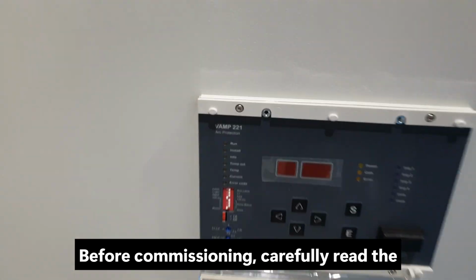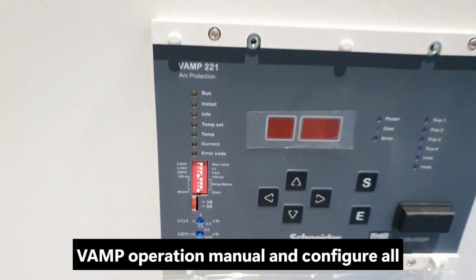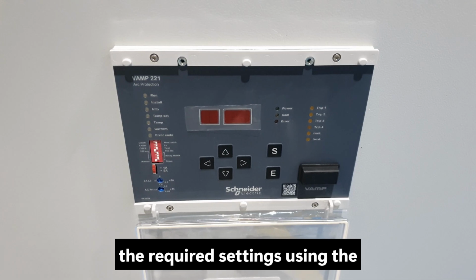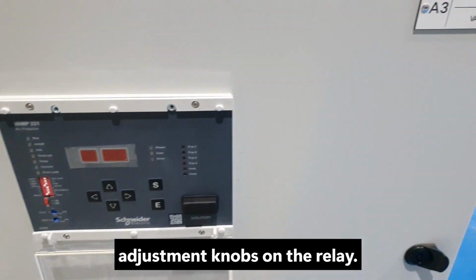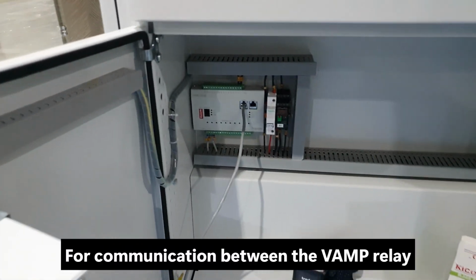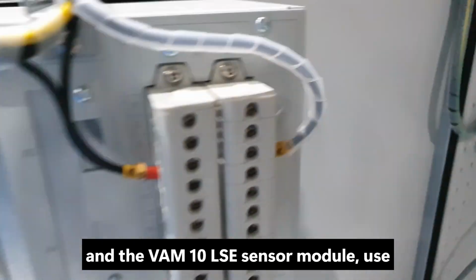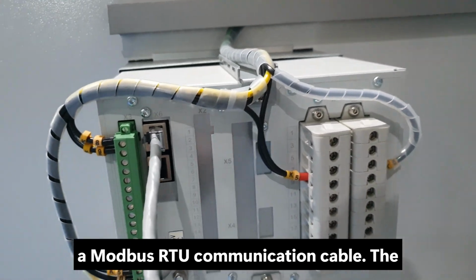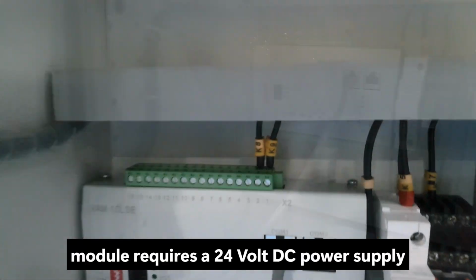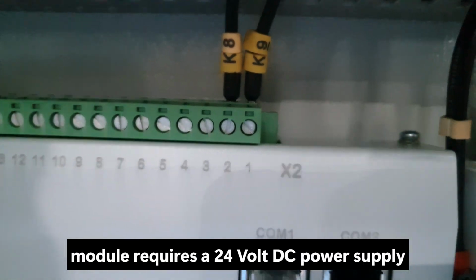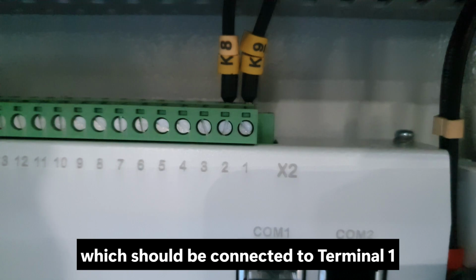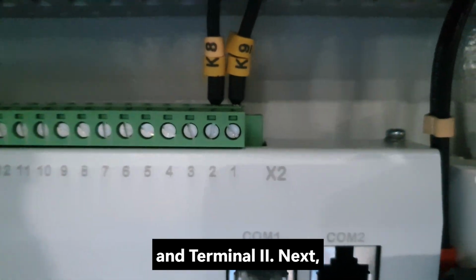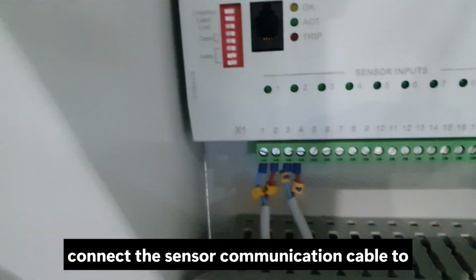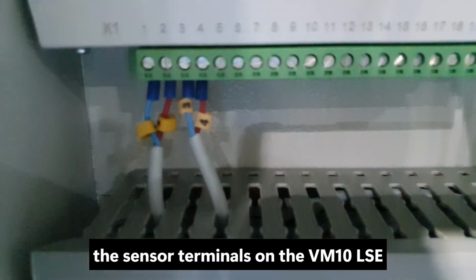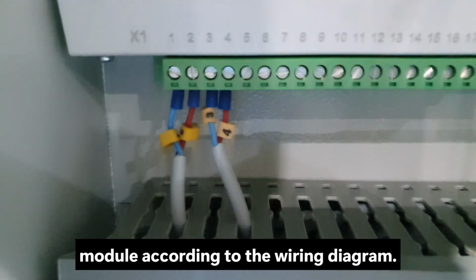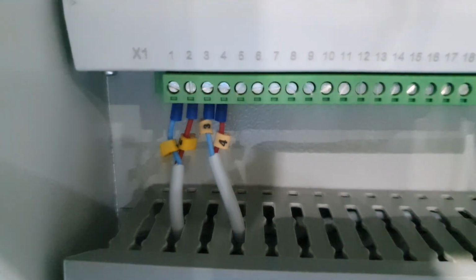Before commissioning, carefully read the VAMP operation manual and configure all the required settings using the adjustment knobs on the relay. For communication between the VAMP relay and the VM10 LSE sensor module, use a Modbus RTU communication cable. The sensor module requires a 24-volt DC power supply, which should be connected to Terminal 1 and Terminal 2. Next, connect the sensor communication cable to the sensor terminals on the VM10 LSE module, according to the wiring diagram.